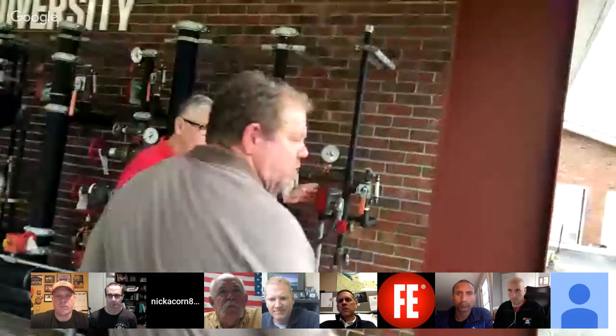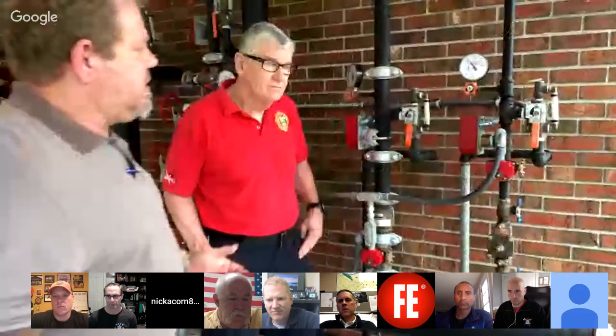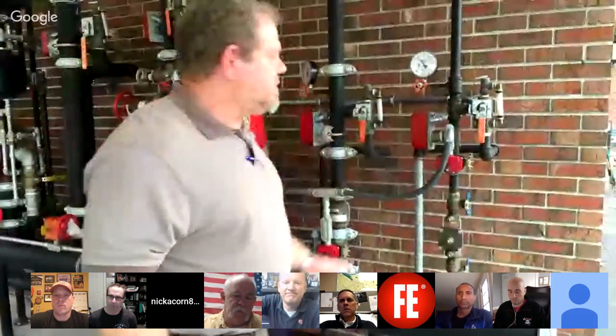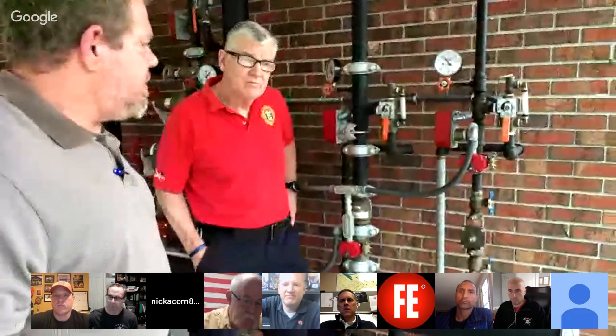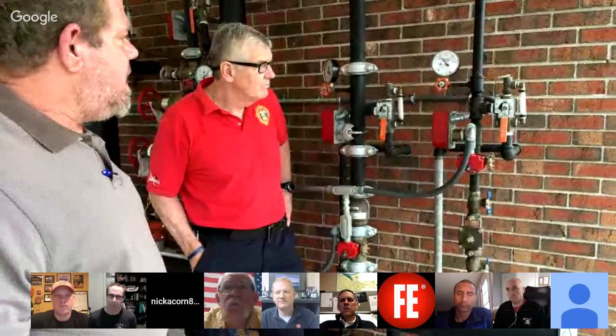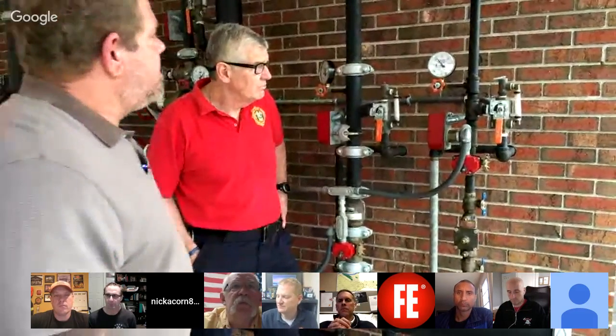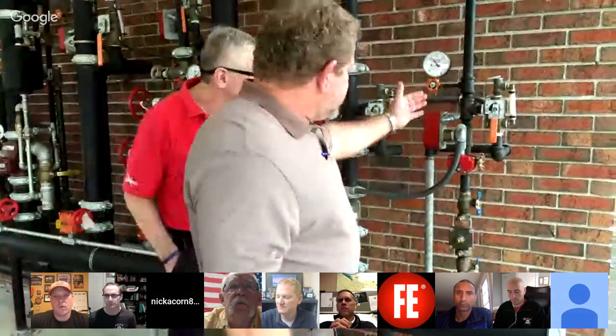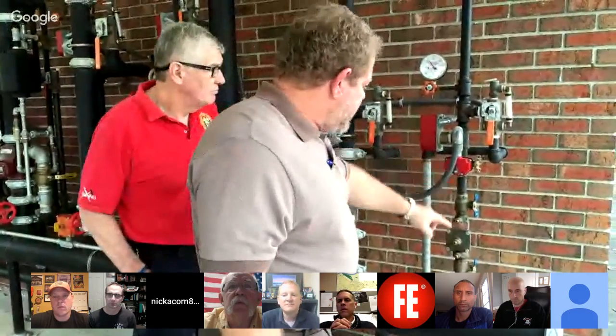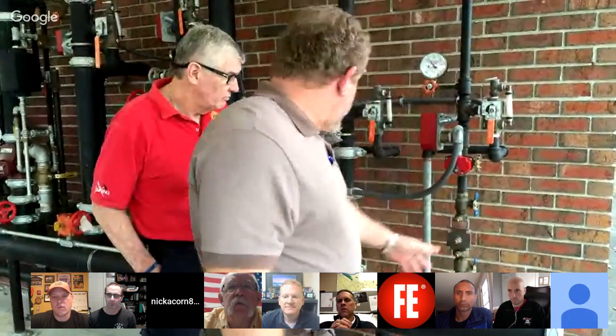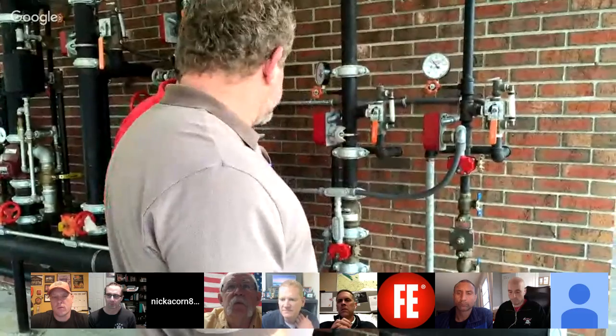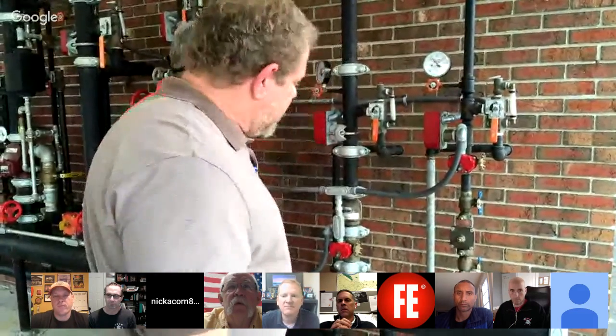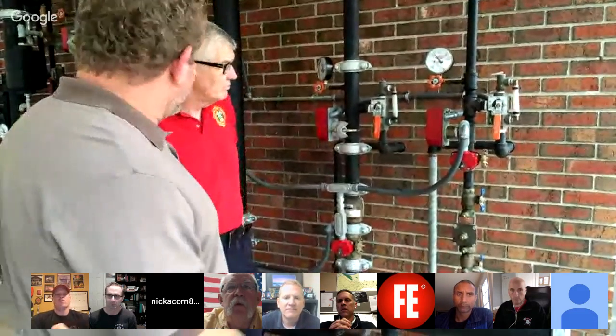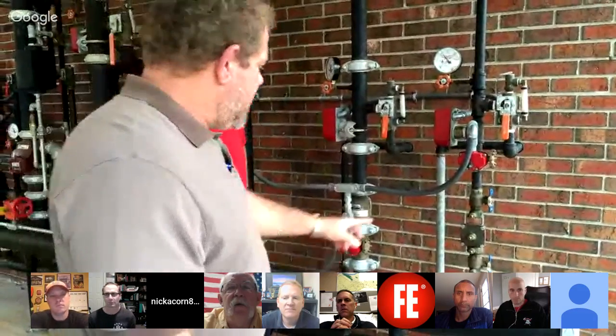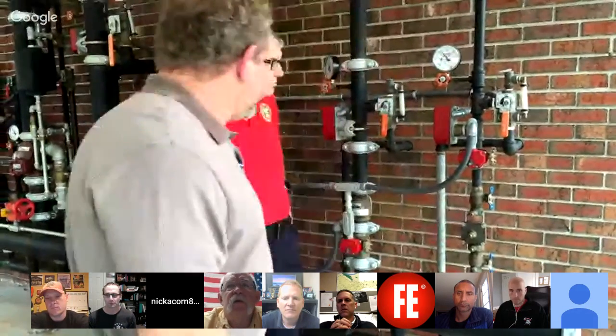So we do a lot of residential fire protection. What we would consider this particular riser an illustration of, like a townhome. So a 13D type system. It's a 1-inch riser, flow switch, tamper switch, and then we actually put a backflow preventer on this particular riser, protecting the water supply. A lot of times, what we'll have is a multi-purpose piping. You have a single lead-in. We take in consideration the meter and effectively protecting the drinking water supply.